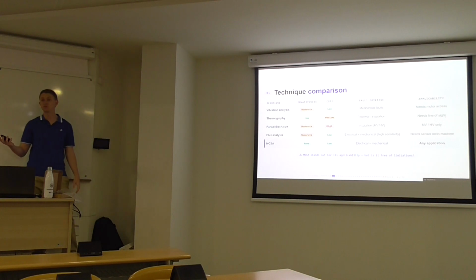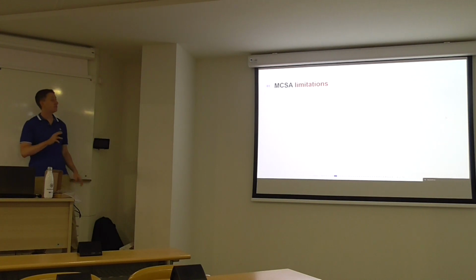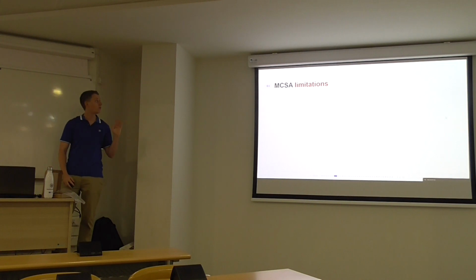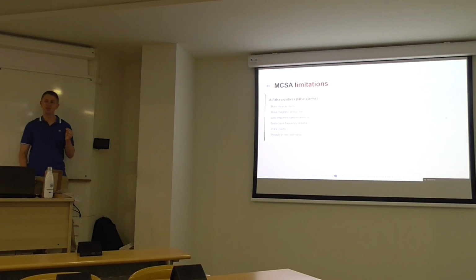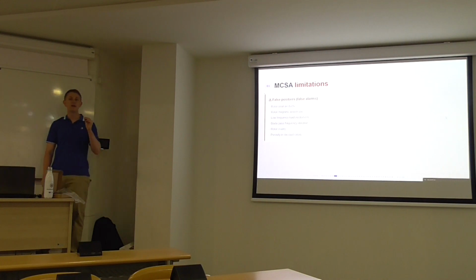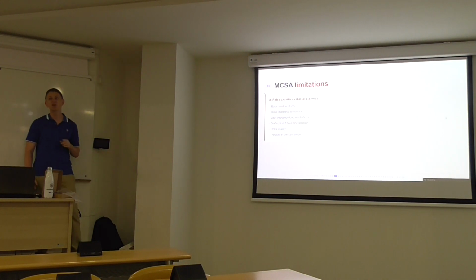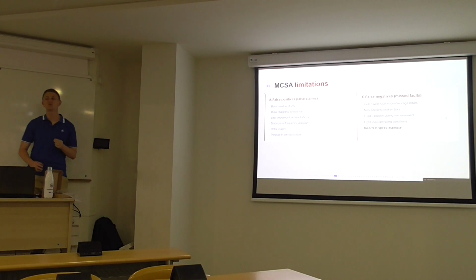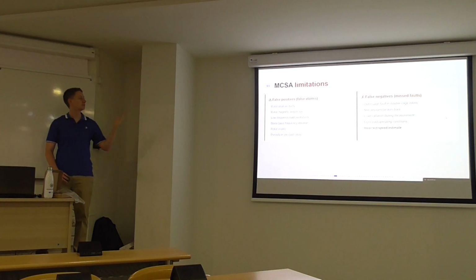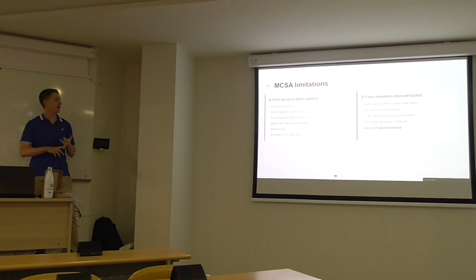But is it free of limitations? Let's see. MCSA is very prone to false positives. A false positive is when we say that a motor is faulty when it's not. And that can be caused by several reasons: rotor slot effects, rotor magnetic anisotropy, low frequency load oscillations, etc. But it is also prone to false negatives. That is to say, that a motor is healthy when in reality it is faulty. And that can be caused, for example, by non-adjacent broken bars, load variation during measurement, and incorrect speed estimation, etc.